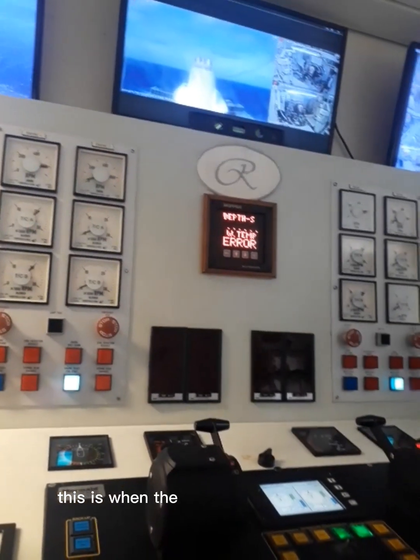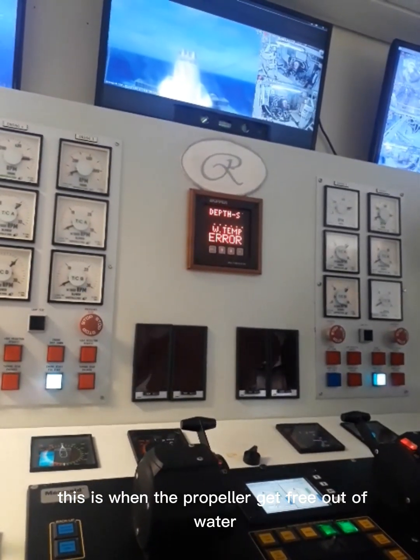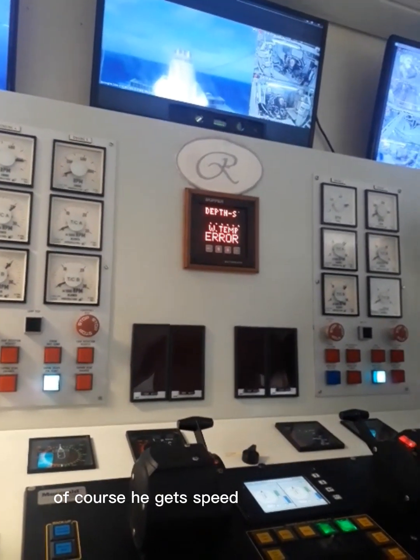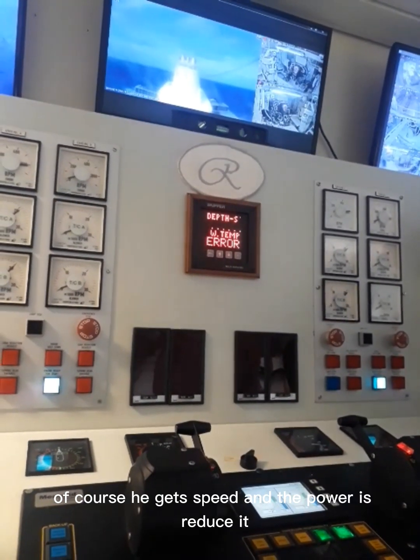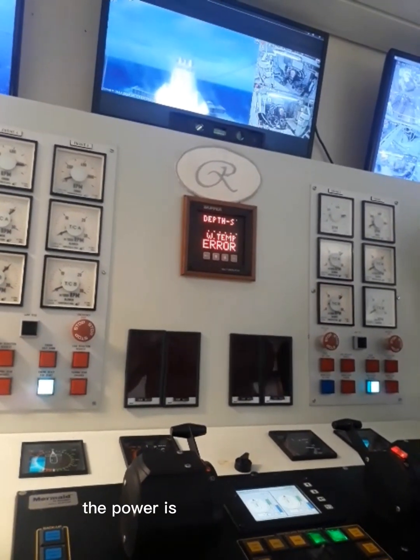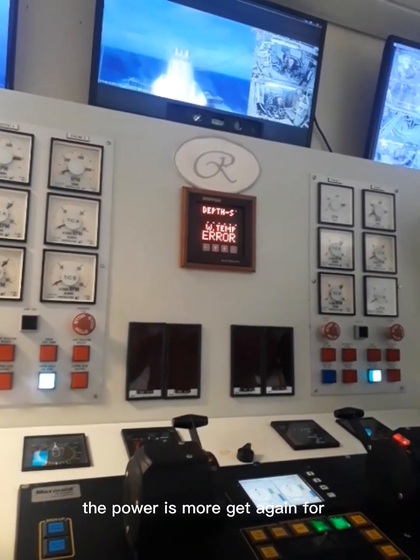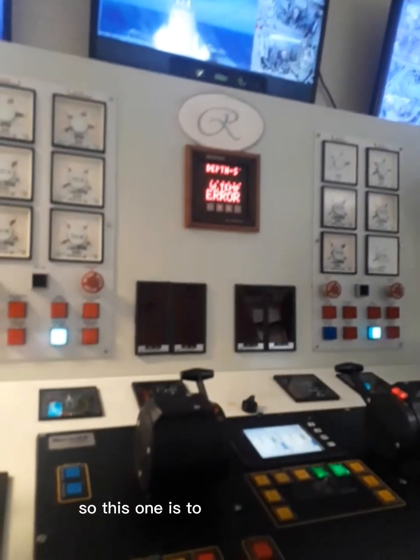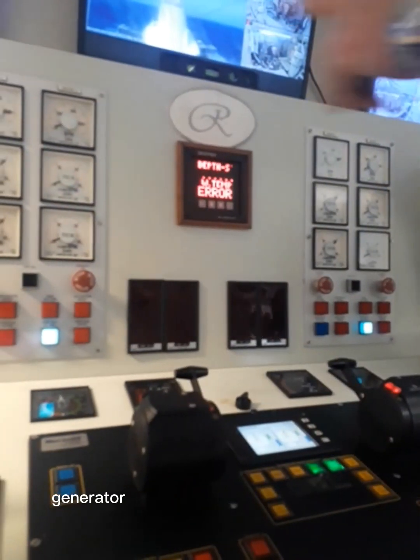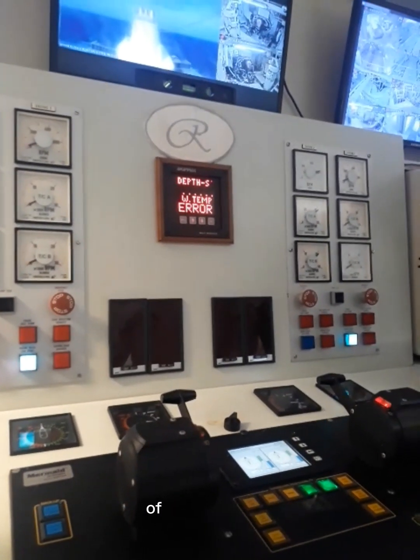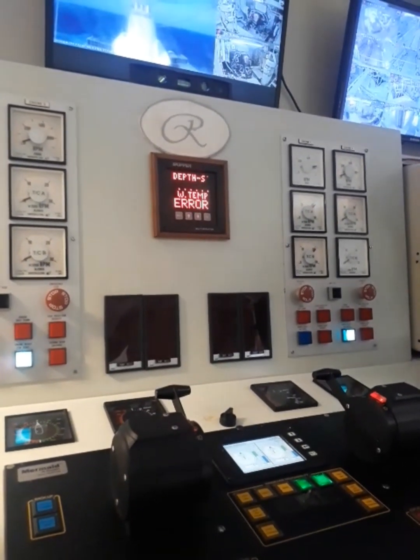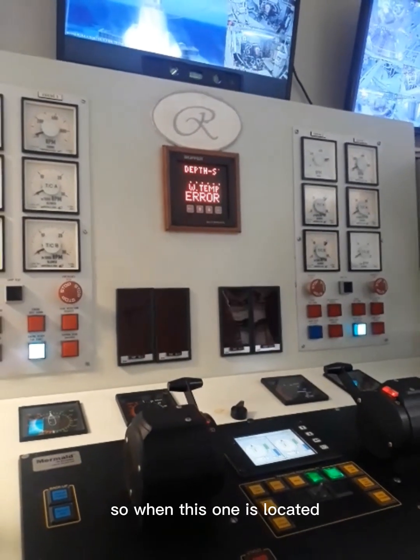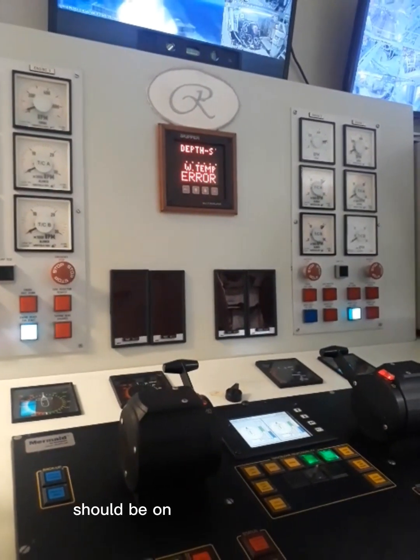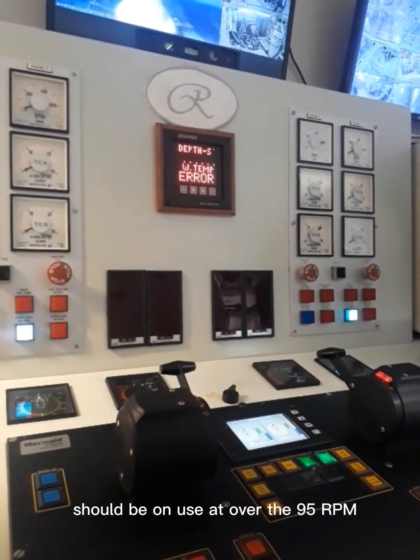This is when the propeller gets free out of water. Of course, he gets speed, and the power is reduced. And then when he is going down, the power is more because he gets again force. So this one is to protect our system, generator load, also the propulsion for this kind of issue. So when this one is locked, should be on use it over the 95 RPM.